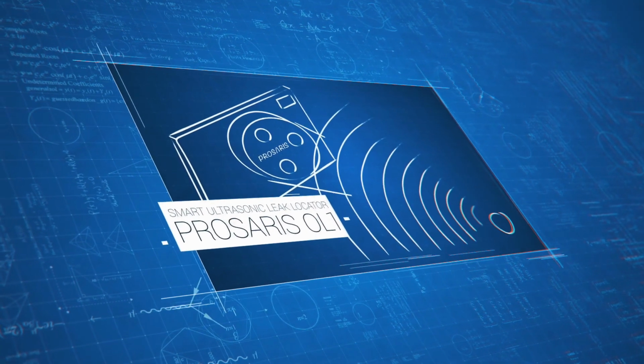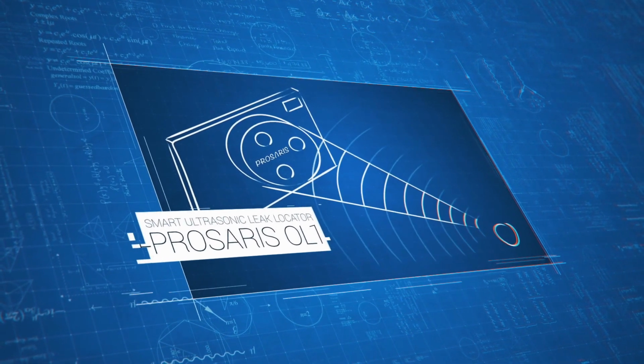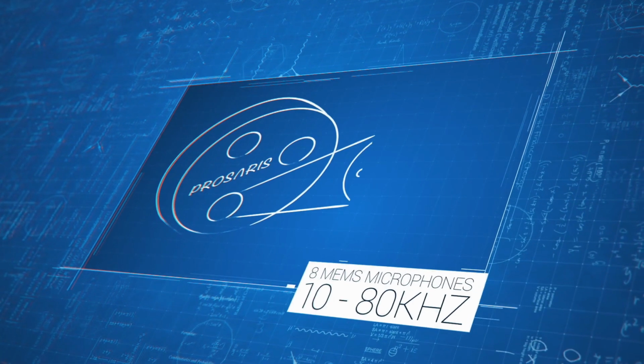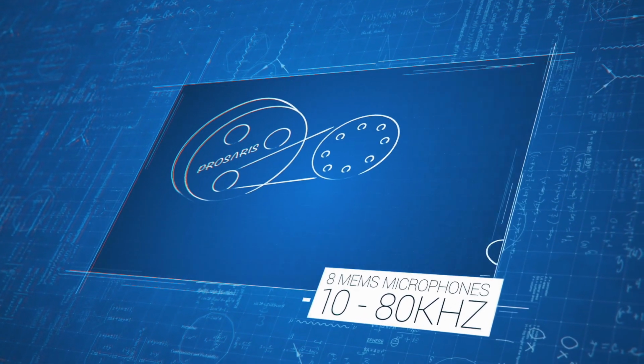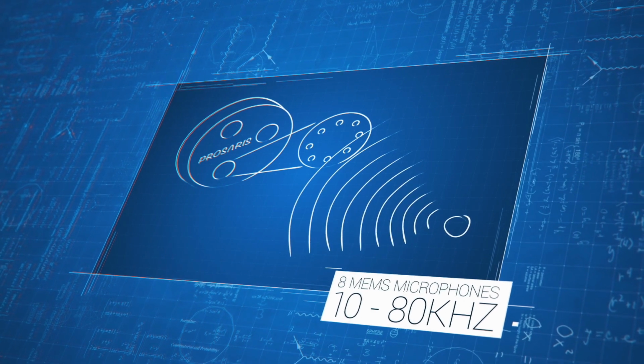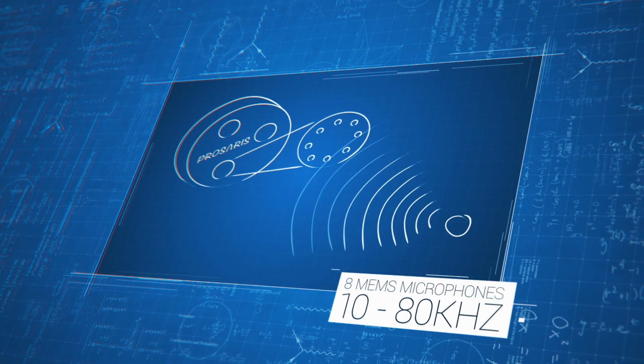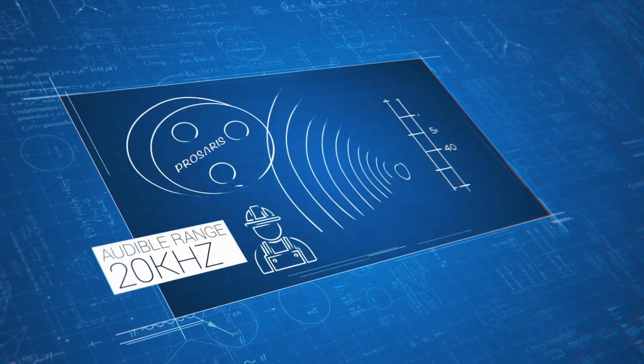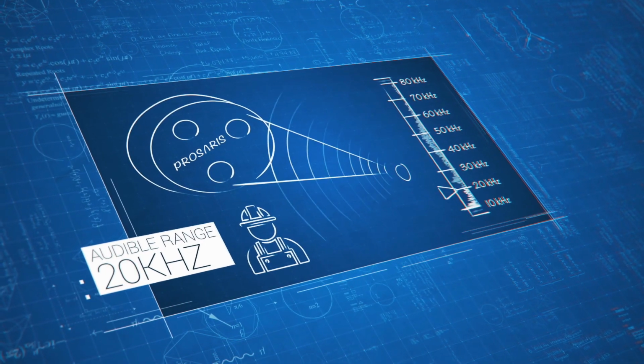Your OL1 is a sophisticated leak-locating microphone array. Each of the 3 discs on the front of your device has 8 MEMS microphones, which are capable of detecting sound energy from 10 kHz up to 80 kHz. The limit of the audible range that we can hear would typically be up to 20 kHz.